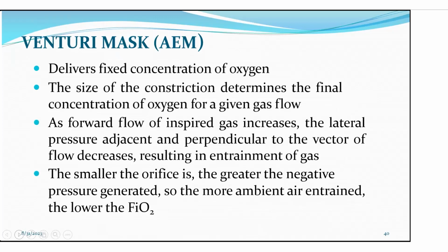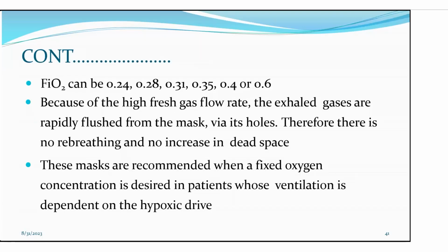We have the Venturi mask. It delivers a fixed concentration of oxygen. The size of the constriction determines the final concentration of oxygen for a given gas flow. As the forward flow of inspired gas increases, the lateral pressure decreases and air is entrained, giving a fractional inspired oxygen of 24, 28, 31, 35, 40, and 60%.